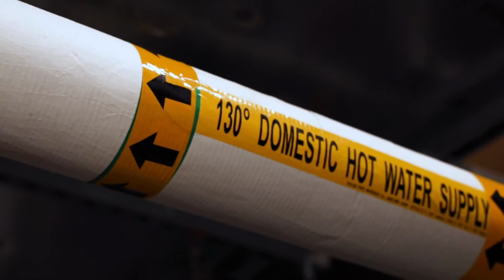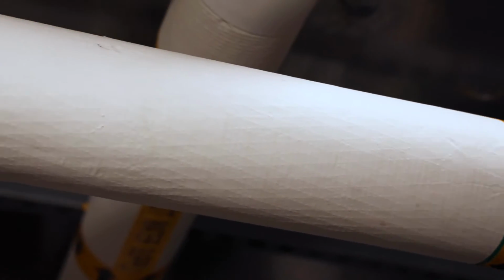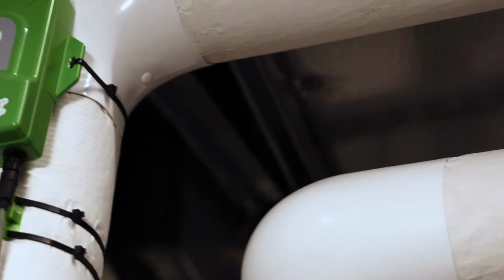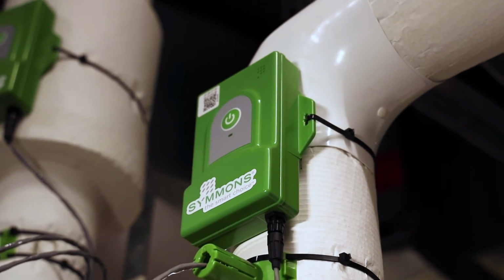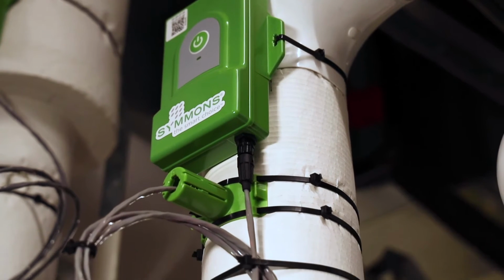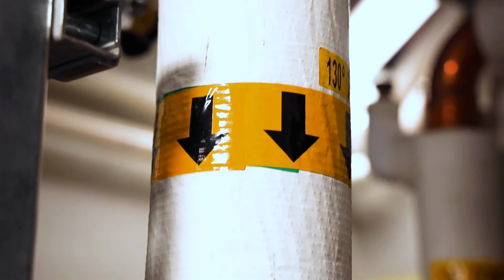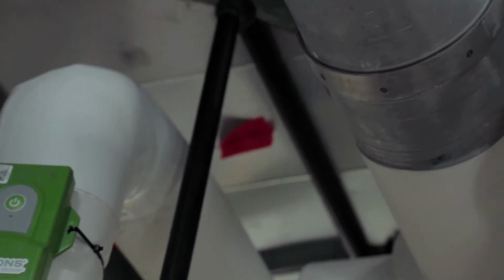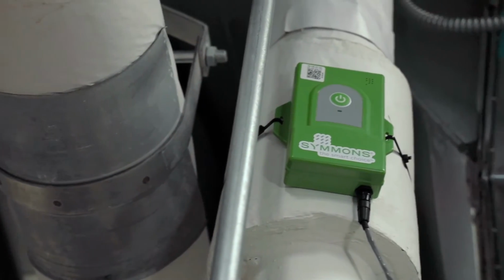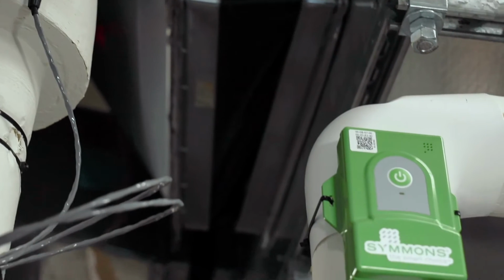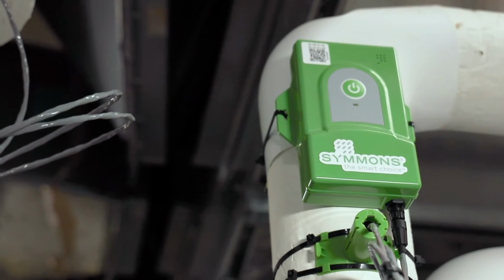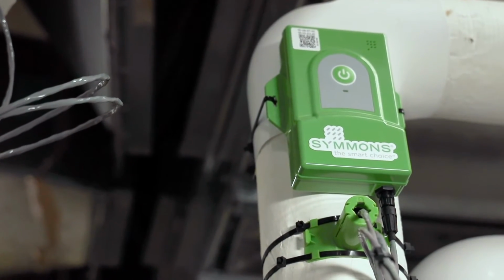Ideally, sensors on domestic hot water systems should track the outlet temperature of hot water from the main mixing valve that's feeding the building. In this case, the sensor should be located on the hot water supply line, about 1 foot downstream of the main mixing valve, on a nice straight piece of piping. For sensors on HVAC systems, sensors should be placed on the main supply and return lines for the cooling unit. Just make sure that the sensor and sensor module are located inside the building and protected from the elements.